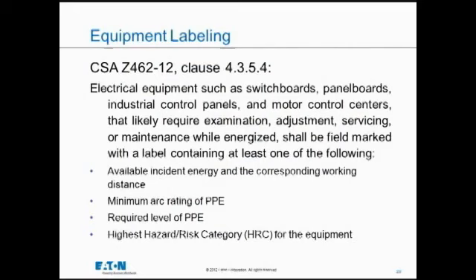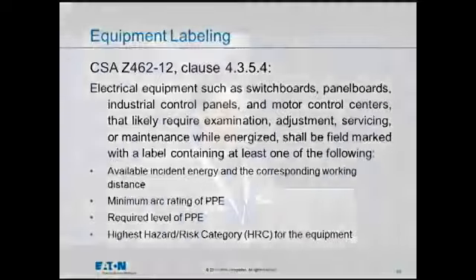Inside of the best practice guide, there is more information on what the arc flash hazard label should include. And you have to pick one of these four. The one that's generally picked is the top one. Energy level, available incident energy, and corresponding working distance. So that's the one that makes most sense to most people, but the other ones can be used. Along with that, you have to put voltage level, the arc flash boundary, and when the hazard analysis was done. They've included a sort of an expiration in the best practice guides of 5 years. They were suggesting every 5 years you go back and look, does our study still make sense?